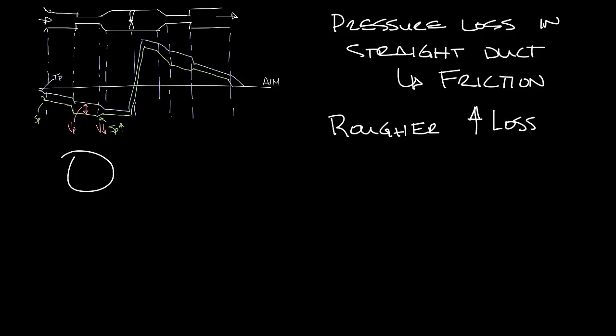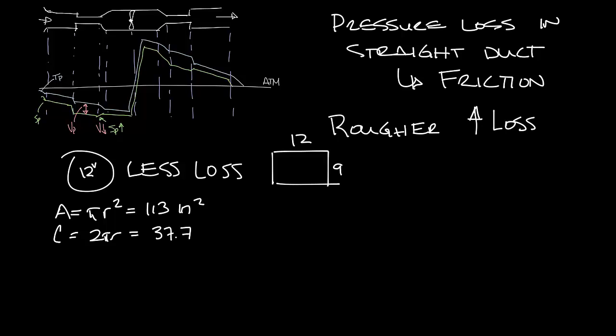As far as the shape of the duct goes, round ductwork will have less pressure loss than rectangular ductwork because there's less surface area. So if you look at this round duct and say it's 12 inches and this is 9 by 12 inch rectangular duct, the area of this 12 inch round duct is pi r squared is about 113 square inches. The circumference of this is 2 pi r and that comes out to be about 37.7 inches.